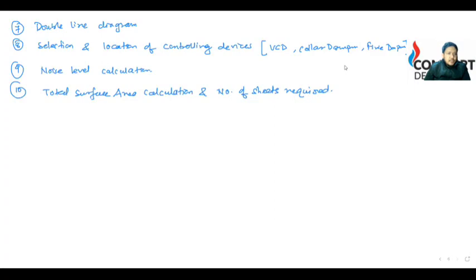Will we do practical on these 9 points? How to do it? Definitely, we can calculate the noise level. There is one formula also, with the help of which we can calculate it. It is 10 plus 50 log V base 10 plus 10 log A base 10, if you put velocity in meter per second and A in square meter.